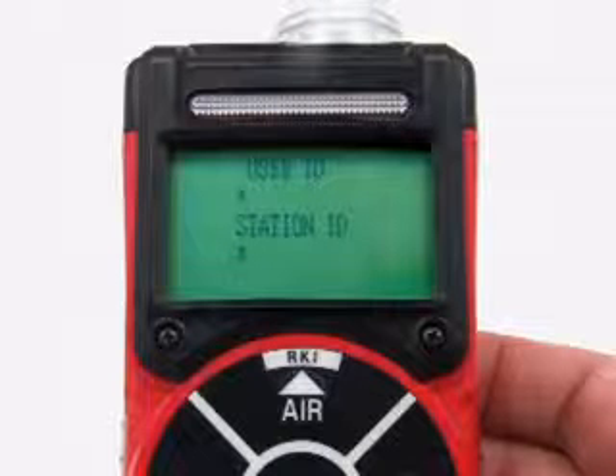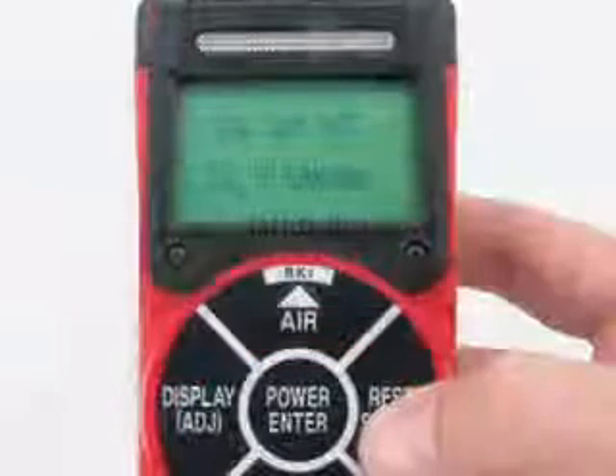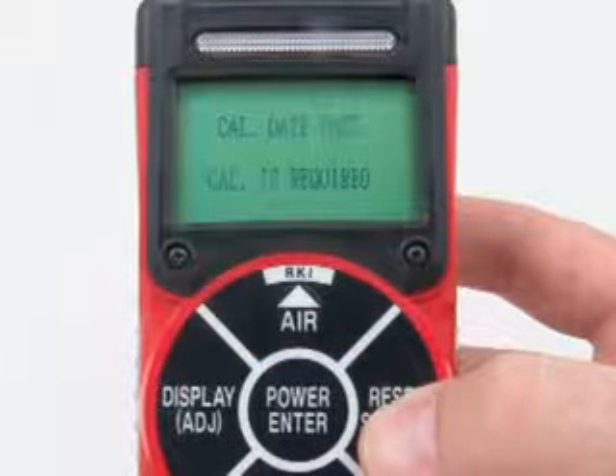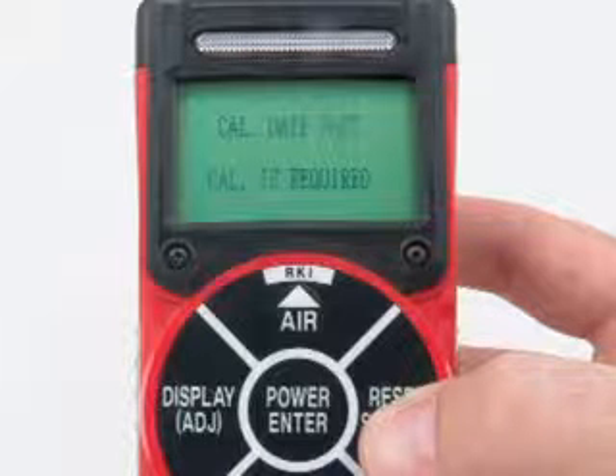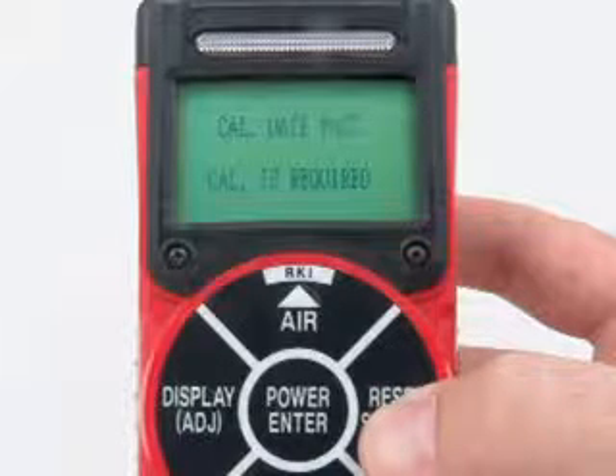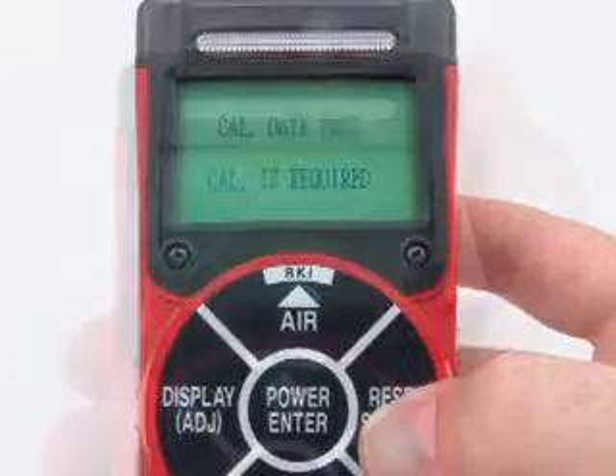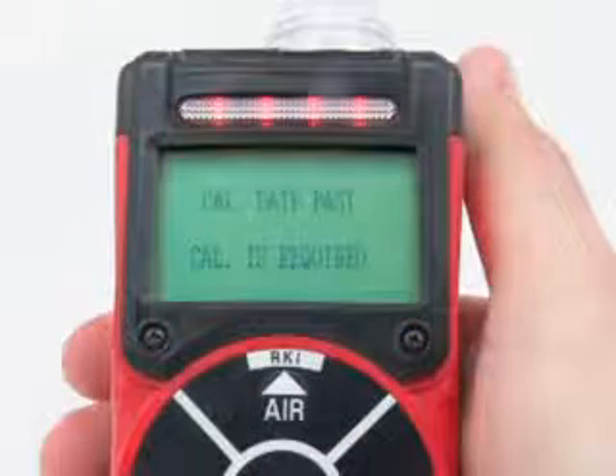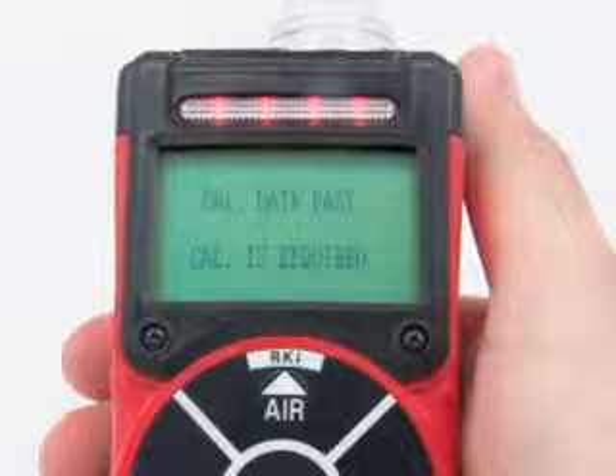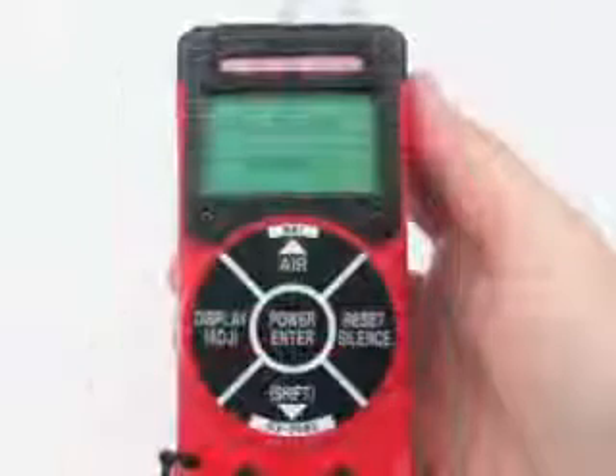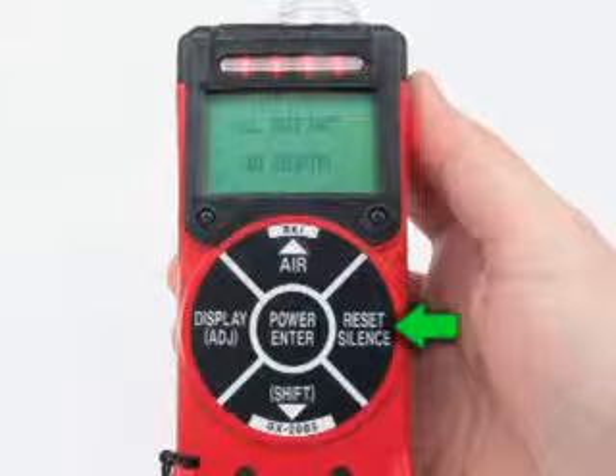If user station ID is turned on, the ID screen displays for a few seconds. After the ID screen, if cal time remaining is turned on, the screen that appears next depends on how the cal expired action is set in the setup mode menu. If the unit is due for calibration and cal expired action is set to confirm to use, the alarm LEDs and buzzer will pulse several times and the vibrator will activate for a second. After this, press the Reset Silence button until you hear a beep to continue.